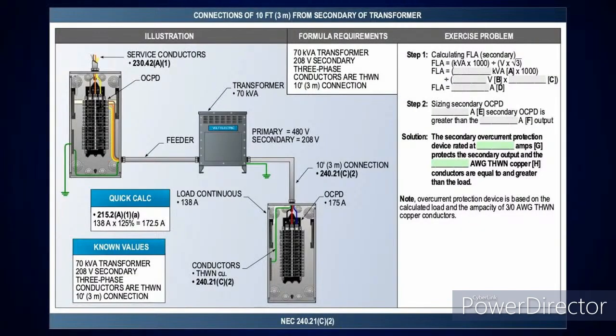And here's another one. We've got a 70 kVA transformer, and you multiply that by 1,000 to get the VA. And what's my voltage? You have a 480 volt primary and a 208 volt secondary. We can tell you the continuous load there. Just do a quick calc to show you the load will be 172.5 amps. Once you do this calculation, we prove that you're large enough.